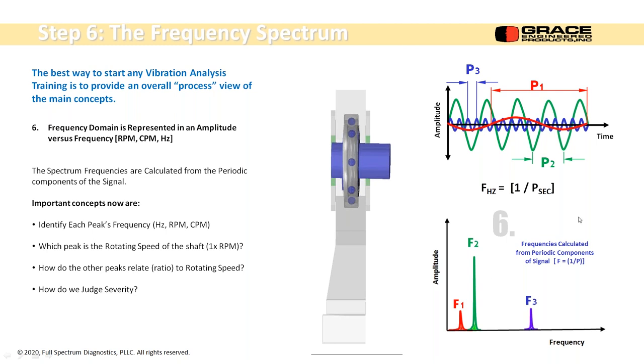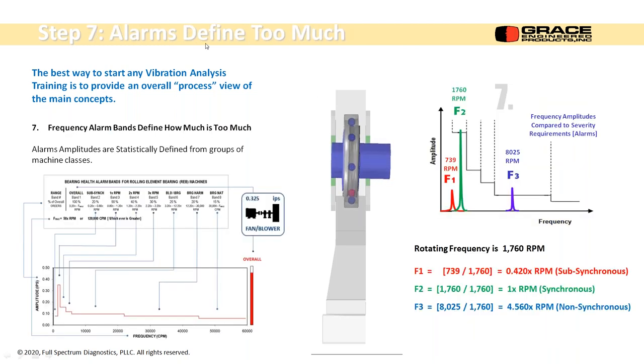How do we judge severity? We don't have any alarms on this yet. Right now, we probably have overall alarms on the waveform. But assuming that we're generating a spectrum, we have to have something to compare it to. The alarms define how much is too much. Frequency band alarms define where all our frequency ranges will have limits. This is a cookie cutter calculation for making this stair step pattern. This pattern is percentages of the overall level. So I take 0.325 inches per second. That's my overall vibration that I'm trending. I can make alarms out of that, fractions of that in the frequency domain.